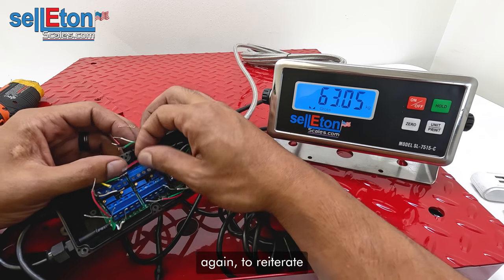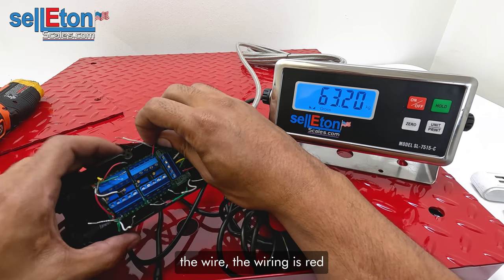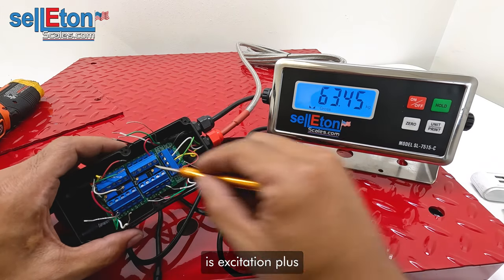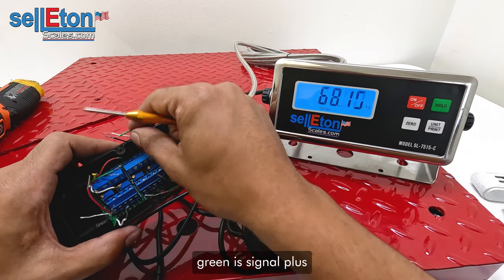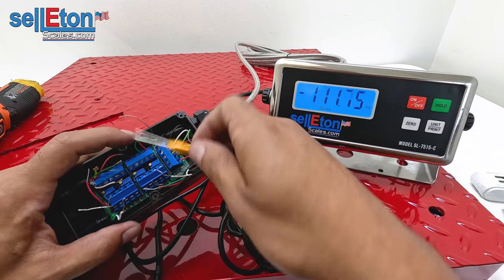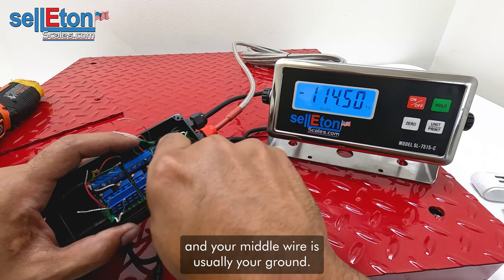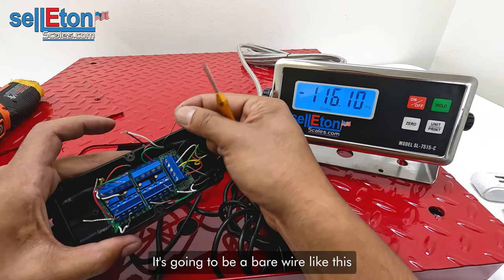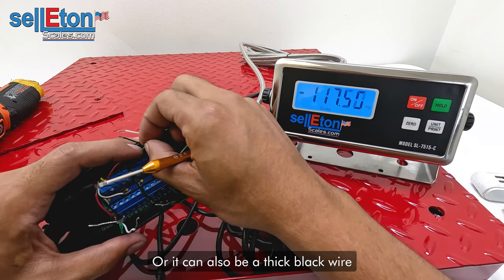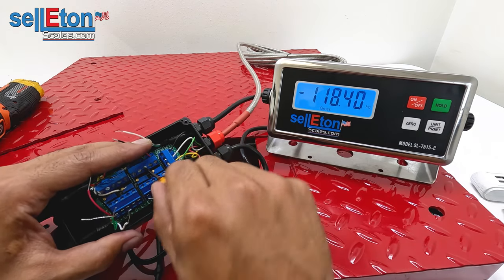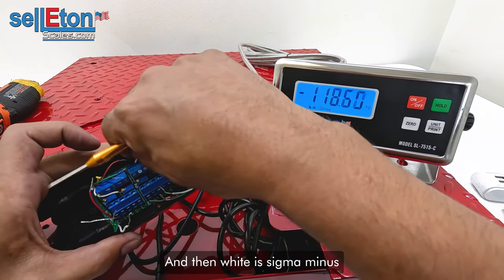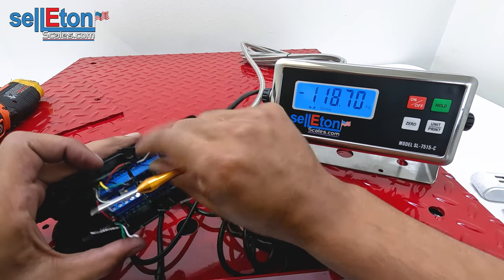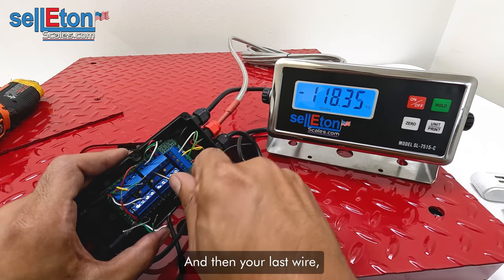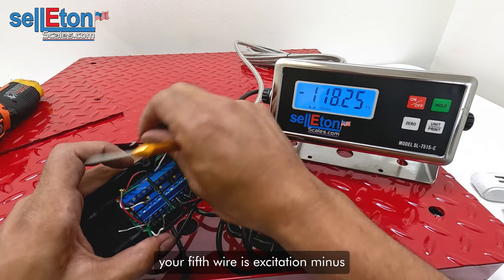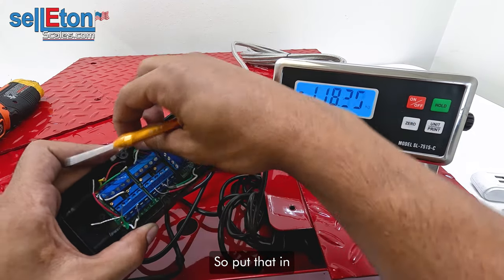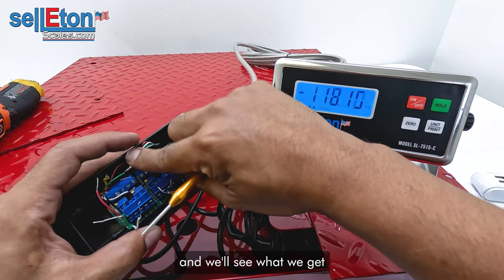So again, to reiterate, the wiring is red is excitation plus. Green is signal plus. And your middle wire is usually your ground. It's going to be a bare wire like this, or a yellow wire, or it can also be a thick black wire or purple wire. And then white is sig minus. And then your last wire, your fifth wire, is excitation minus. So we're gonna put that in and we'll see what we get.